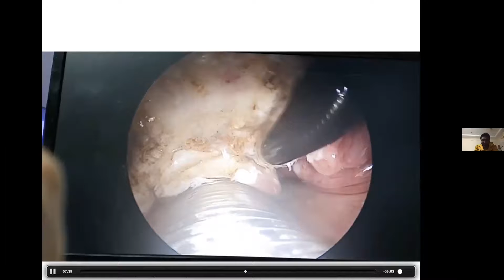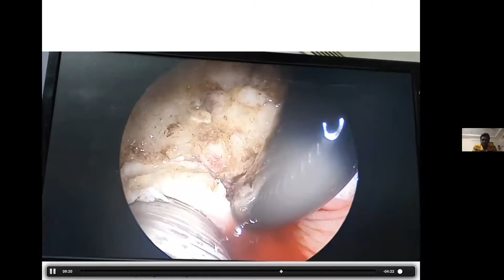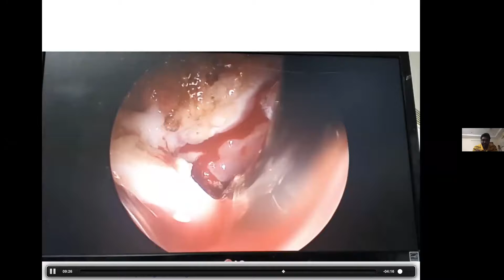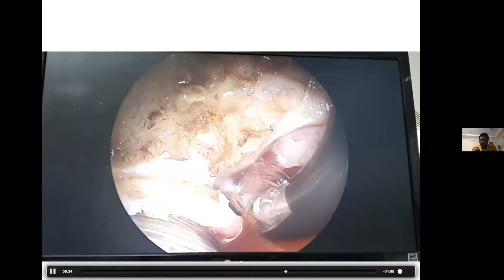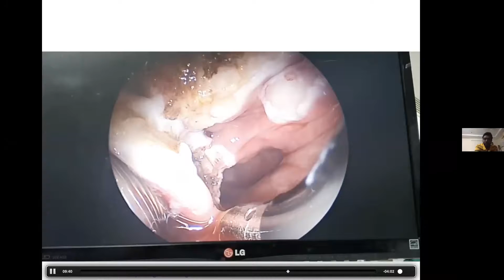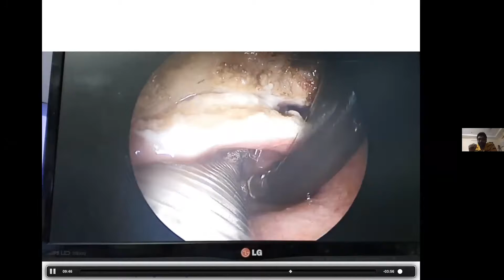I am going to the other side. In case I get any bleeding, like what I'm about to show you here, because I have an adequate exposure, I can immediately use the same wand in a coagulation mode, and I can keep a contact mode. So far I was using a near contact mode, but for doing an ablation or a coagulation, I go for a contact mode, and I keep it in the contact mode for at least 4 seconds, and until I achieve a hemostasis, I do this again and again, provided it is a capillary ooze or a venous ooze.